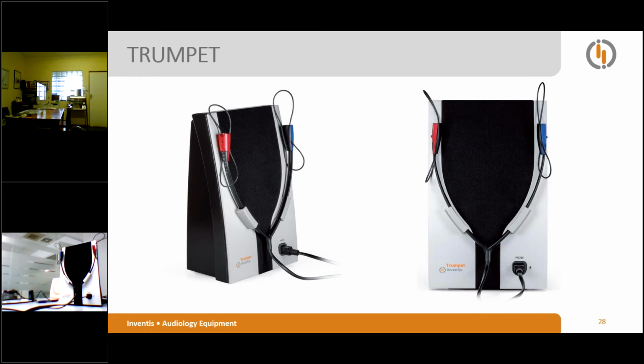In fact, we can think of having adjusted properly the gains of a hearing aid only when the quality of the sound reproduced by the hearing aid itself is optimized according to the patient's needs and preferences. Such a balance between audibility and optimization of the stimuli quality can only be obtained by measuring the sound produced by the hearing aid directly in the ear of the patient who wears the device. Okay, so it is very important to use a real ear measurement system to be sure that the patient feels comfortable with the hearing aid she wears. Absolutely. Okay.